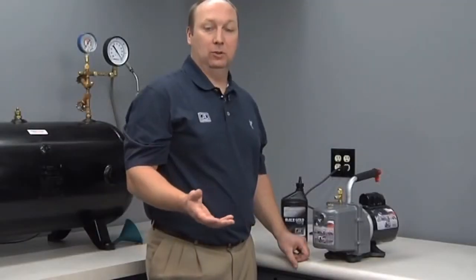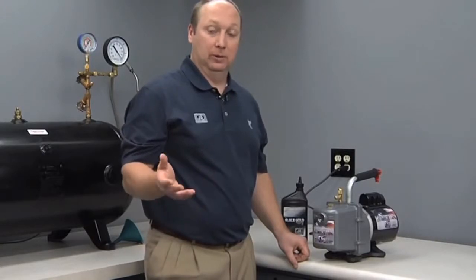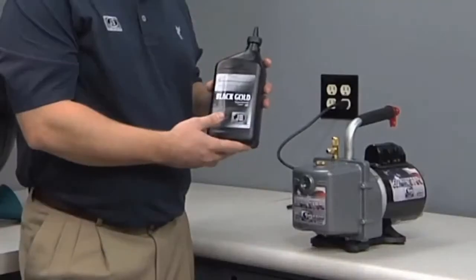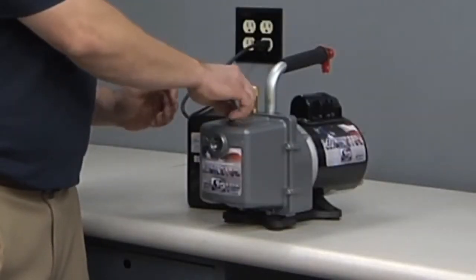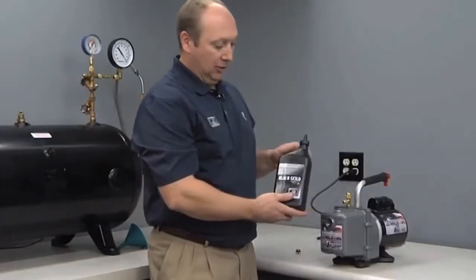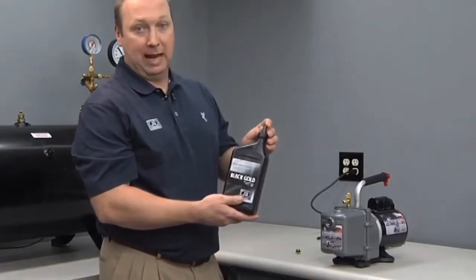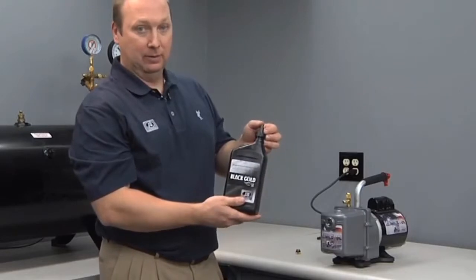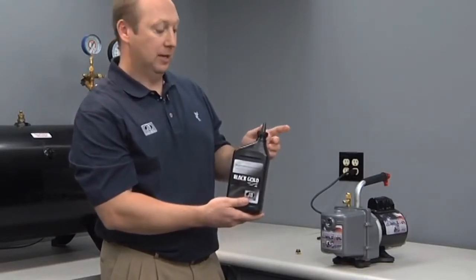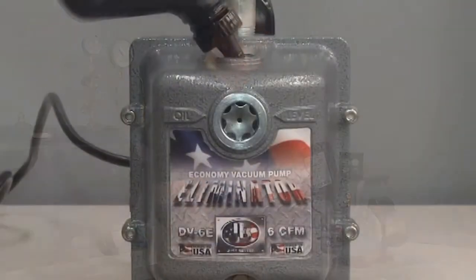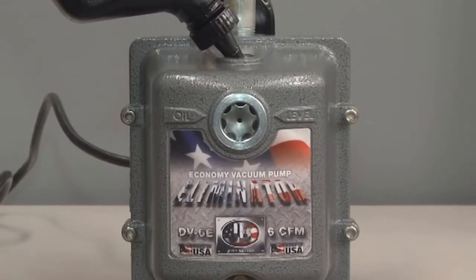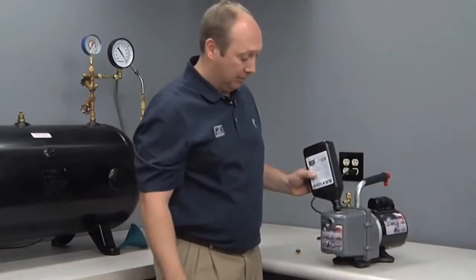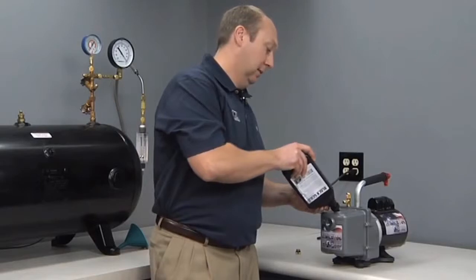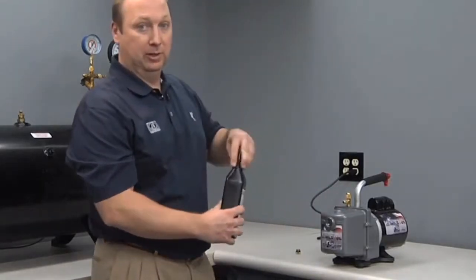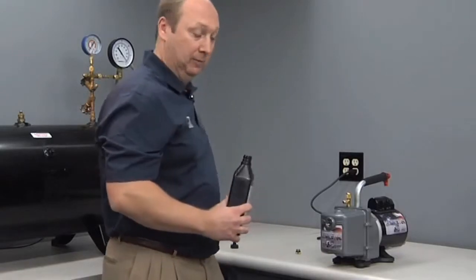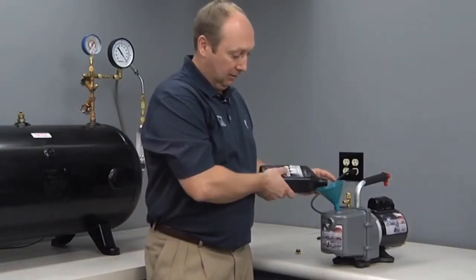The pump will accommodate up to 22 ounces of oil, which is great for larger jobs where oil gets contaminated more quickly. There are a couple of ways to fill the eliminator. Simply remove the oil fill cap. All JB oil quarts come with a conical shaped cap for easy fill. You can cut it off depending on the speed of fill that you desire. Simply put it in the hole and allow it to fill. Ensure that your oil drain is closed at this time, otherwise oil will come out of the bottom. The other way to fill your JB eliminator vacuum pump is to simply use any funnel, remove the cap completely, and fill.